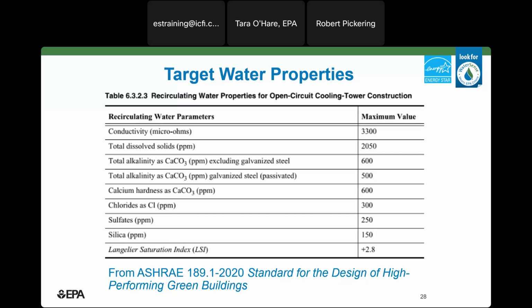This information can be helpful in identifying your cycles of concentration limit. So, for example, if your limiting parameter is total dissolved solids or TDS, you can identify your target cycles by evaluating incoming water quality. If your incoming water quality's TDS is 1,000 ppm, your tower may only really be able to safely run at 2 cycles because 2,050 divided by 1,000 is approximately 2. However, if your incoming water has a TDS of 200, you might be able to achieve 10 cycles of concentration.